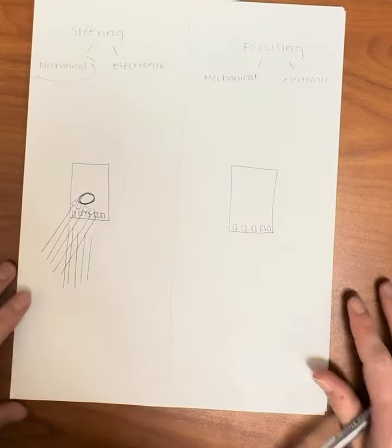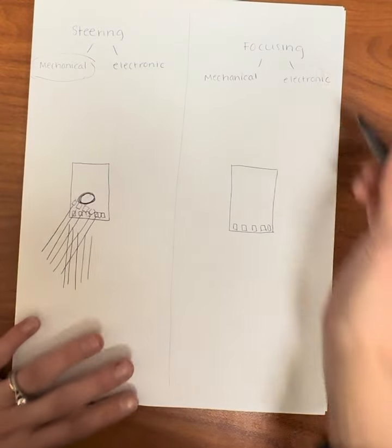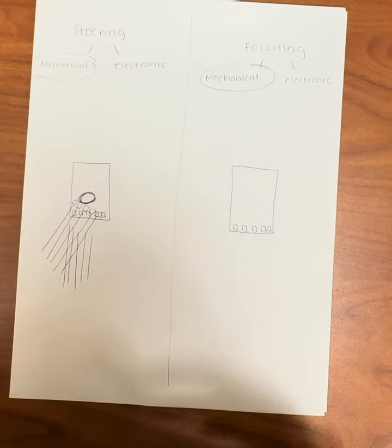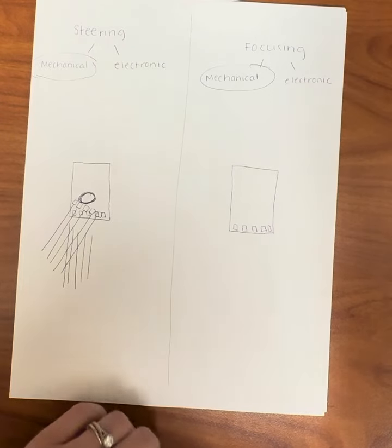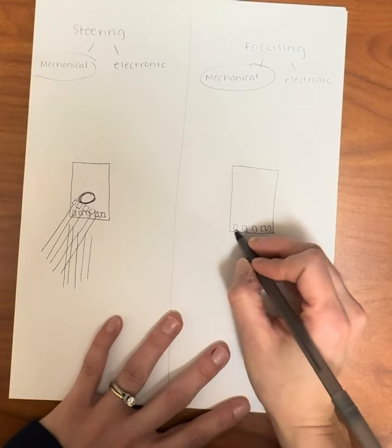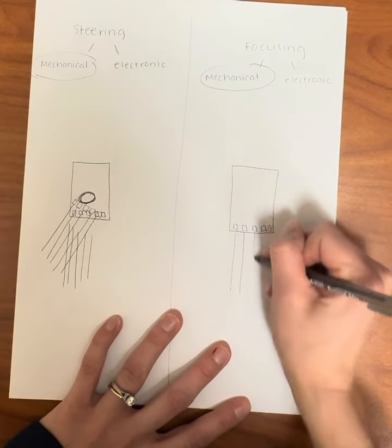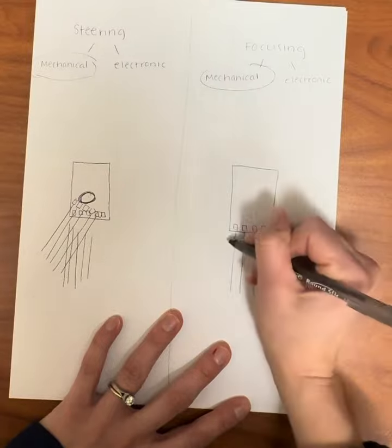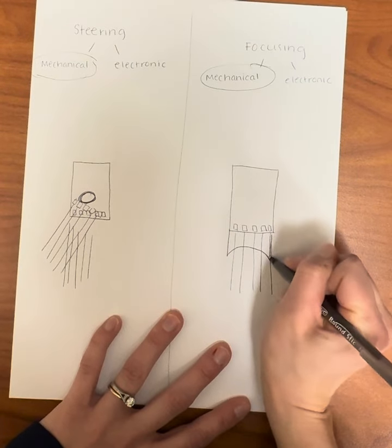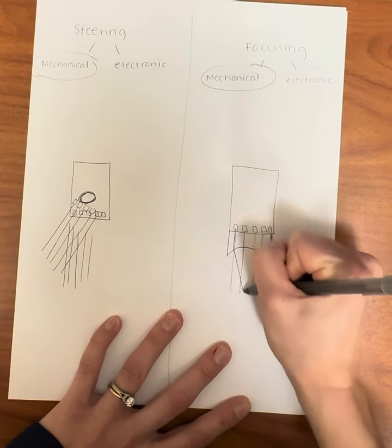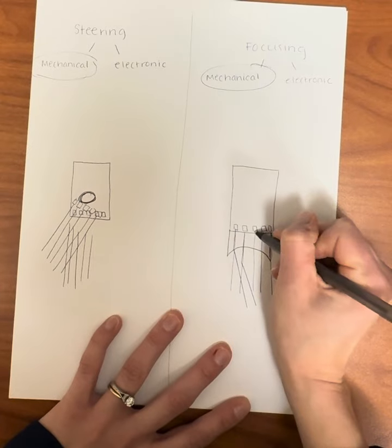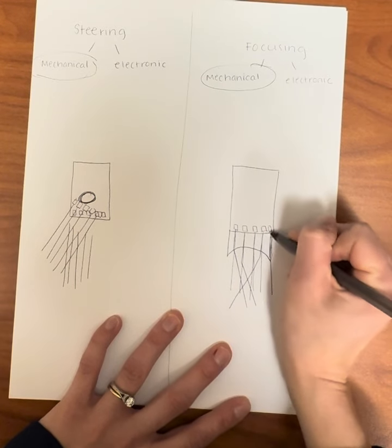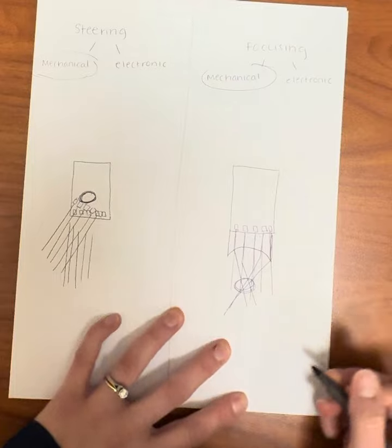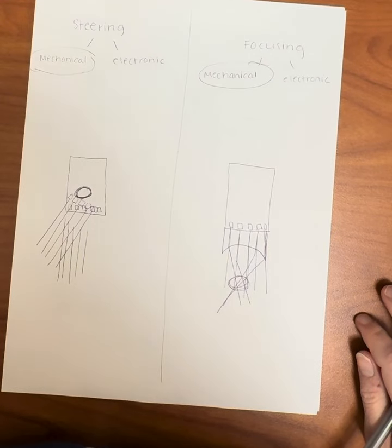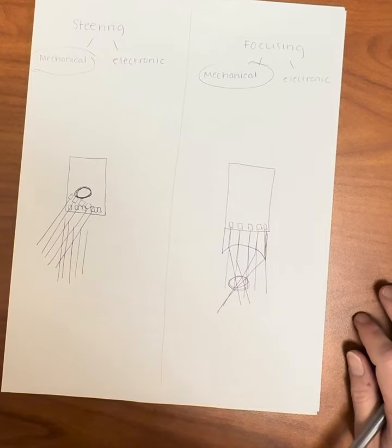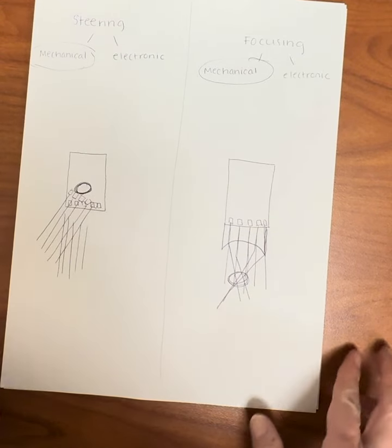For mechanical focusing, they would take a lens, either internal or external, and they would put it on the transducer in order to focus the beam. So if you can imagine that typically these beams are going to come straight down out of the elements, and if we added a curved lens, a convex lens here, what happens is that the beam comes and then bends and winds up focusing, and we wind up with this focal part, this more narrow part of the sound beam. So you could mechanically steer and mechanically focus an ultrasound transducer.